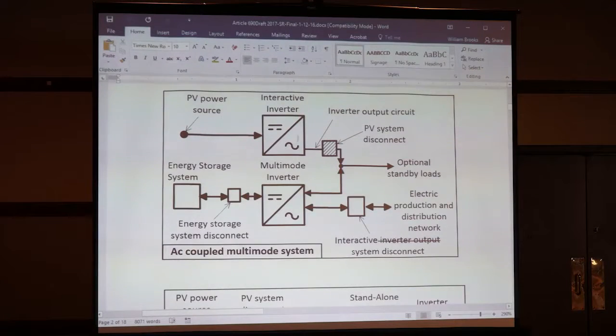So the interactive inverter here is interacting not with the grid, it's interacting with the multimode system, right? Which is why we changed the term from utility interactive inverter to just interactive inverter. That was a very calculated change, because our interactive inverters are no longer just interacting with the grid. They're interacting with other inverters. They're interacting with both current source inverters and voltage source inverters, and loads and everything else. And they may have to communicate with one another. There may actually be communications between the multimode inverter and the interactive inverter. There's all kinds of different configurations that may be necessary.